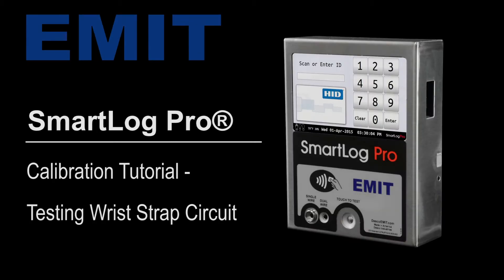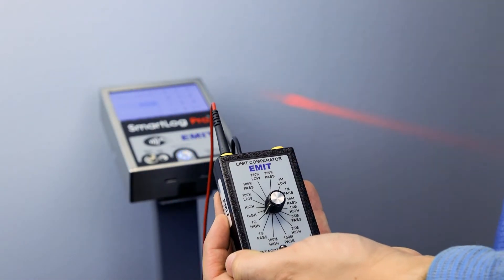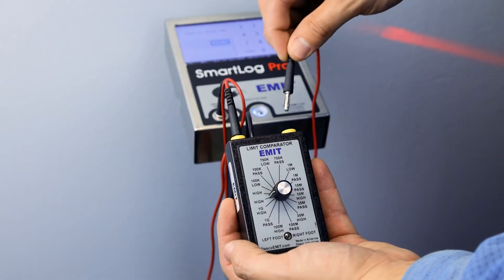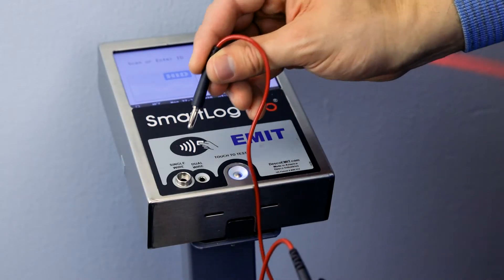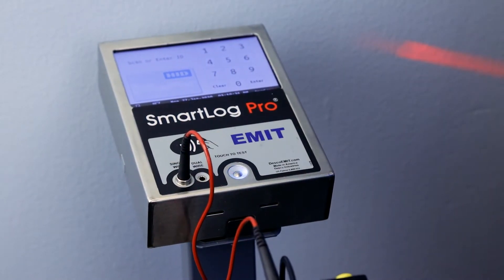Testing the wrist strap circuit. Connect one of the test leads to the top of the Limit Comparator. Connect the opposite end of the lead to electrical ground. Connect the second test lead to the top of the Limit Comparator. Connect the opposite end of the lead to the single-wire jack located on the face of the SmartLog Pro.